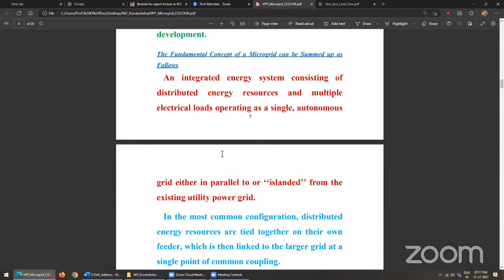Whenever a microgrid is grid connected, the voltage and frequency will be dictated by the grid, so they need not control the voltage and frequency of the microgrid. But when a microgrid operates in islanded mode, isolated from the grid, you have to have at least one DG for droop control, such that voltage and frequency need to be controlled. Renewable sources may be there, but you have to have droop control DGs so that voltage and frequency can be controlled, because it is isolated from the grid.